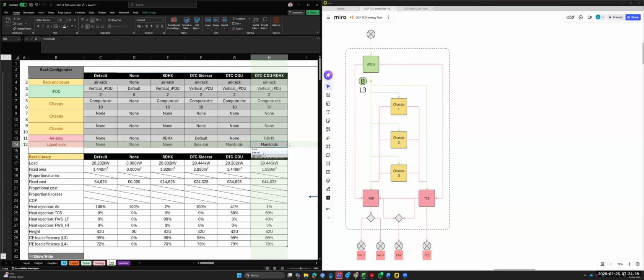So in that case, liquid to air cold plate cooling via a sidecar is defined at the rack level. As you can see in this case, there is no heat rejection to TCS, all of the heat is essentially rejected to the air side and received by whatever cooling there is at the chassis level, at the cluster level.